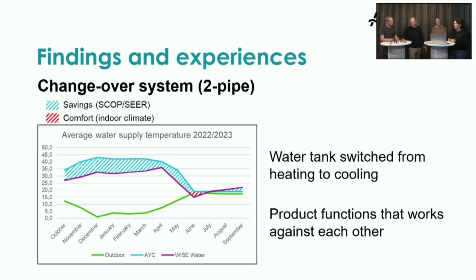Yes, after the system was taken into use, we continuously monitored the logs to see that all units were functioning well. We could see that the chiller was changing operation mode from cooling to heating rather often in spring. Then we synced the logs from the chiller, air handling unit, shunt group, and DCV system, and discovered that one of the standard functions in the air handling unit was triggering the change of the tank.